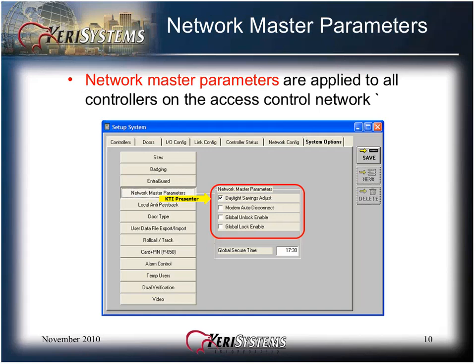Depending on the age of the system, firmware upgrades may be required. Minimum firmware for the current daylight savings time is 8.4.49 for PXL 500 series controllers, 6.3.61 for PXL 250 series controllers, 7.6.05 for EntraGuard Titanium and Silver telephone entry controllers, and 9.1.06 for the EntraGuard Platinum series controller.